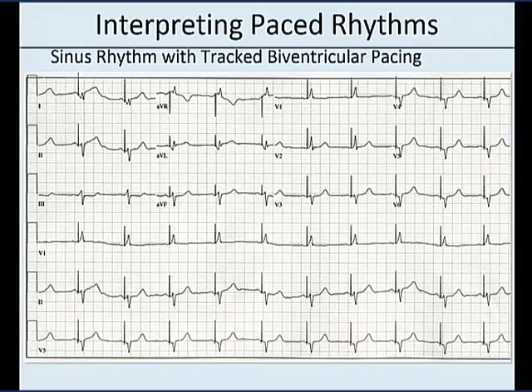All right, troubleshooting. You'll be called on by your nurses to say, you know, this guy has a pacer, it's not working, why don't we see this? There are two major categories of this. Why don't I see ventricular pacing? That might be because you don't see any spikes at all, or you see spikes but they don't capture. Of this first category, you got a dead battery. That's my problem. I should have followed up the patient a little bit better than that.